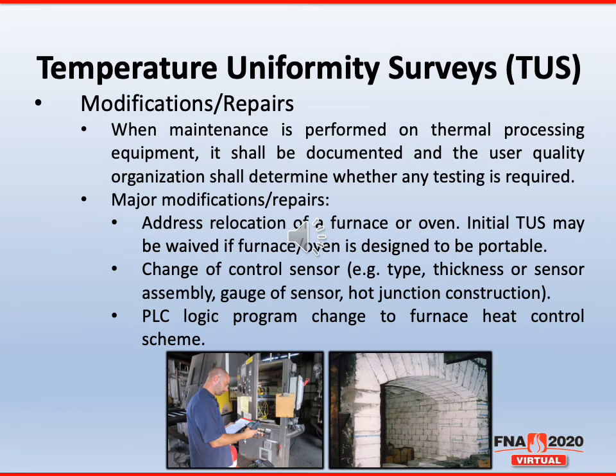So those who are familiar with Rev E, when it came to maintenance, modifications and repairs, there were two sections. There was major modifications and repairs, and they listed various items that were considered a major modification and what were considered repairs. The repair section has actually been removed, and we list out the major modifications. So when any kind of maintenance is performed on any thermal processing equipment, it shall be documented, and the user's quality organization shall determine whether any testing is required. So in other words, quality will need to get involved after any kind of maintenance or repair is done to the furnace, and handle if a temperature uniformity survey needs to be performed.